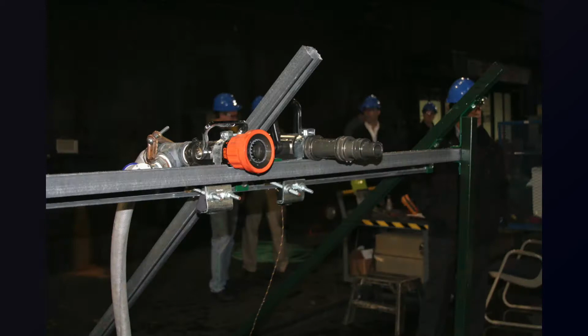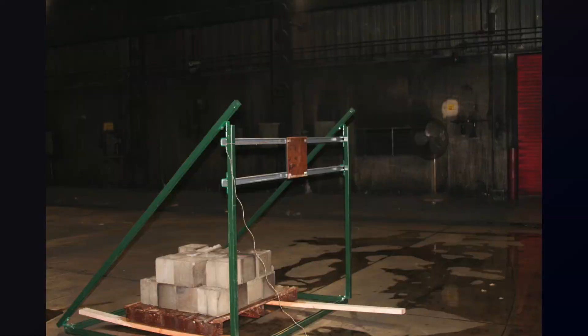UL conducted several tests using two different kinds of nozzles, a smoothbore nozzle and a fog stream nozzle, and several different water sources: municipal water, pond water, and salt water. They directed a hose stream at a copper plate energized up to 1,000 volts, and moved the nozzle closer and further apart to see at what point current was detected back at the coupling.